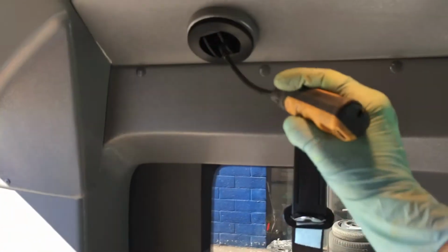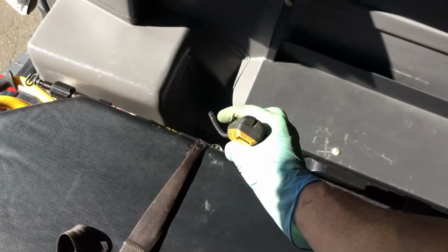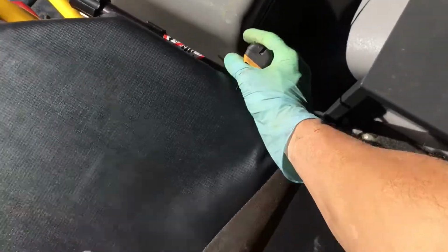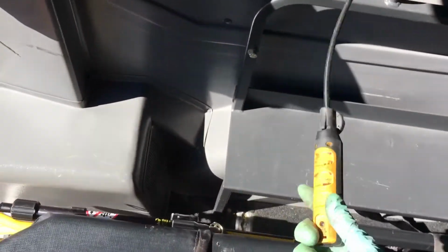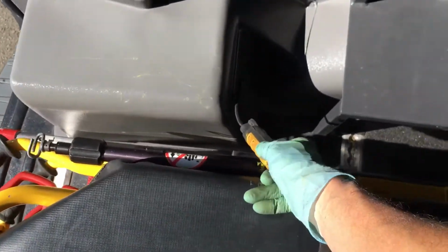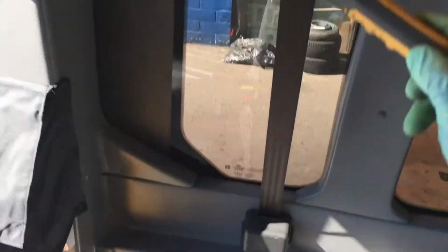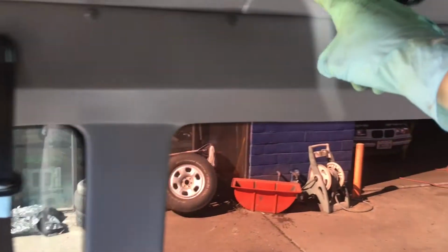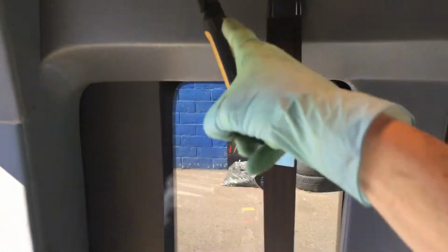So here's our closest duct. Here's our evaporator. That's where the air goes in, right there. So if you want to take your TD across the evaporator on this one, you can put a temperature sensor right there. This is the nearest one. So you'll get your truest reading out of the nearest duct. After that, they start picking up temperature. The farther you go away, the more temperature you'll pick up. So you want to get to your closest one. And let's see what our outlet is right there.